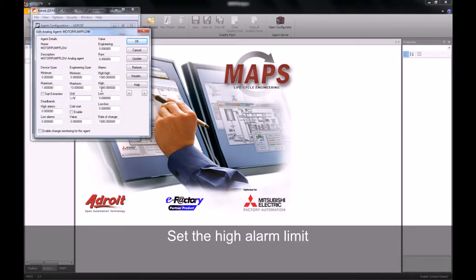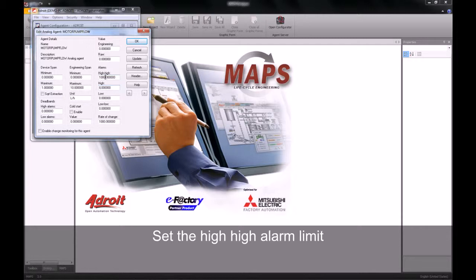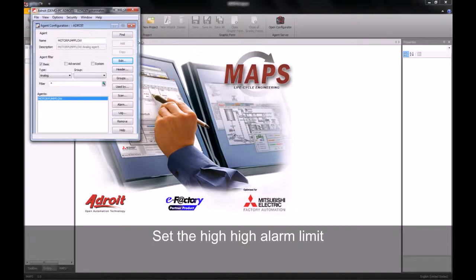We can then go and edit our alarm limits. Our high alarm limit, or first up alarm, will be given a value of 8, and our high-high or second up alarm a value of 10. We hit the update button to accept all changes and click our OK button.